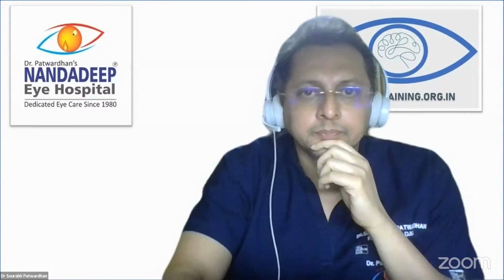These filters, the 5 and 10 micron filters, are outside the OR. They are not inside the ward, so they need to be cleaned every week. We actually take out the filters, wash them, dry them, and then put them back. They are on the terrace or somewhere outside. The HEPA filter, which is in the ward, does not require cleaning.